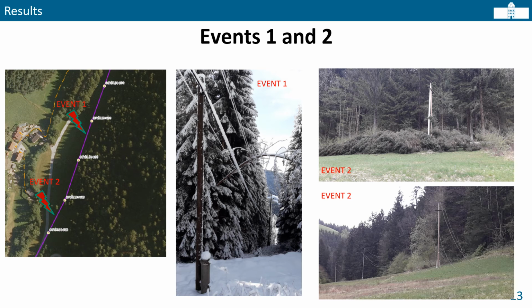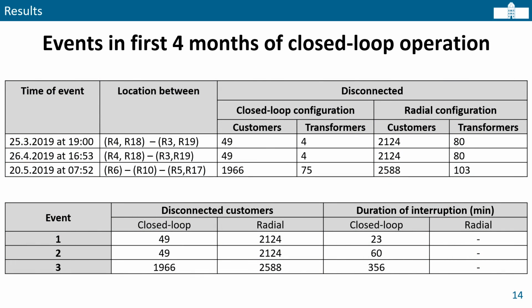The event number 1 was caused by a tree. It was a phase-to-phase short circuit, and the event number 2 was also caused by a tree, which broke the conductors. These are results of the analysis. In the case of closed loop operation, 49 customers and 4 transformer substations were without supply, while in the case of radial configuration these numbers would be much higher. Also, the duration of interruption was for the events number 1 and 2 pretty short and acceptable.